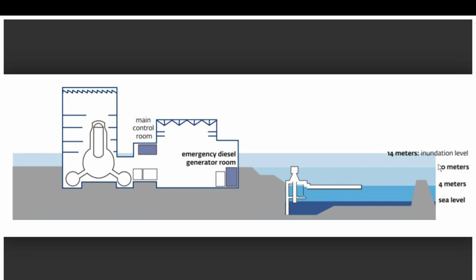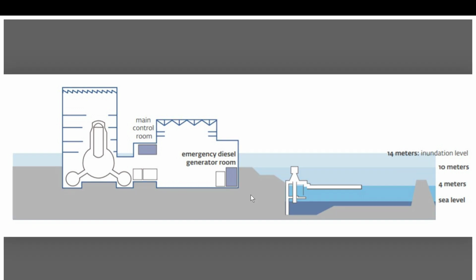However, the actual tsunami on that day was 14 meters tall. So even if they had made a bigger seawall, that might not have helped things at all, because the main thing was that the diesel generator room got flooded. The fuel tanks actually got completely washed away, and then they had no backup power.